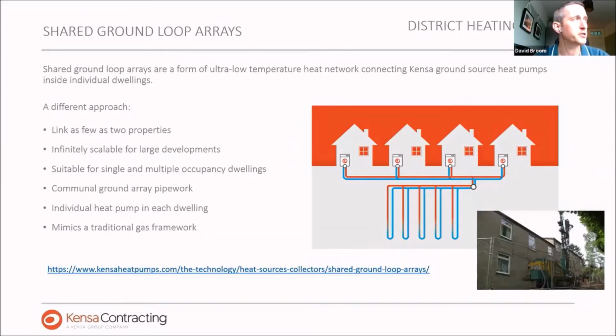With shared ground loop, we take a traditional district heat network and turn it on its head a little bit. We use the ground array, where we gather the low grade energy from the ground that's used to deliver the energy to the system, and make that communal. So we have a network of boreholes linked together via a central manifold and then distribute out to individual heat pumps within each home. This means that all of the energy that we're gathering is in a sense communal, and that allows us to qualify as district heating, but each end user has an individual heat pump within their home. This means that their billing is just naturally part of their domestic energy bill, because the heat pump is downstream of the individual's meter.